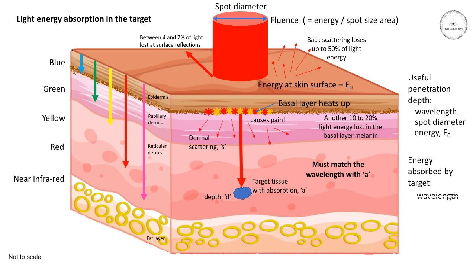Useful penetration depth depends on the wavelength of the light, the spot diameter, and the energy. The energy that's finally absorbed by the target depends on the wavelength, the depth of the target, the absorption coefficient of the target, and the scattering coefficient of the surrounding medium.